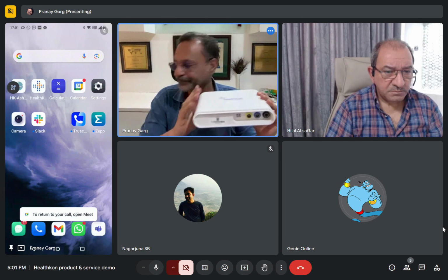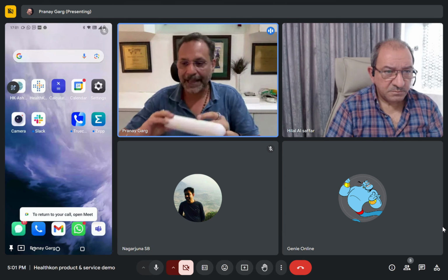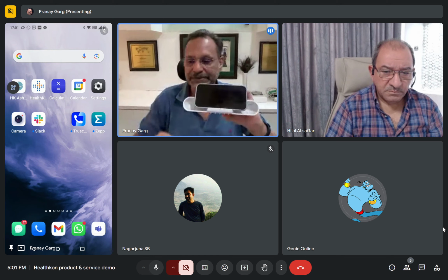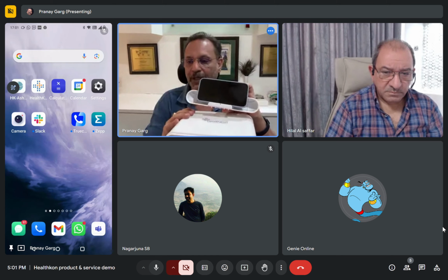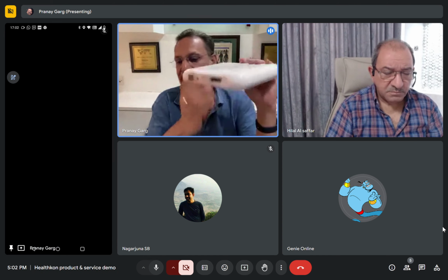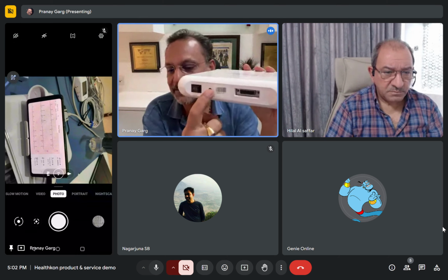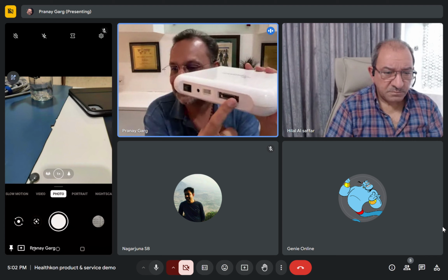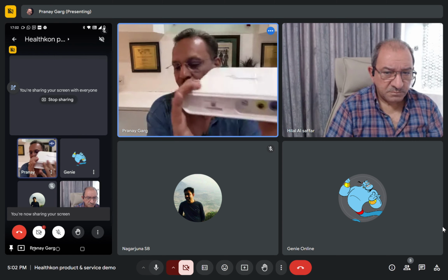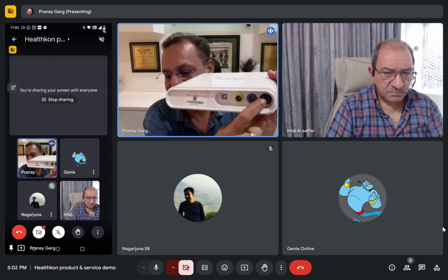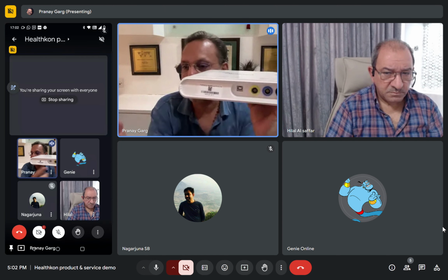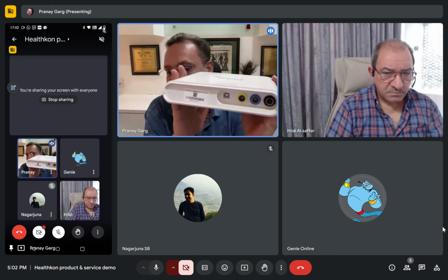This is the device. Even the cap doubles up as a display. So you open the cap, this becomes your stand. Your display becomes your phone, and otherwise it is the cap. This has the power switch here. This is a cable, this is your 15-pin, which the commercially off-the-shelf ECG cables would be attaching to. No special requirement. This is push fit, color coded push fit kind of connectors, which anybody can do.